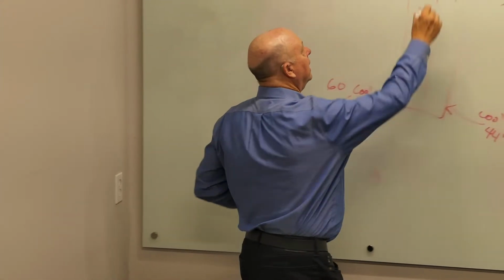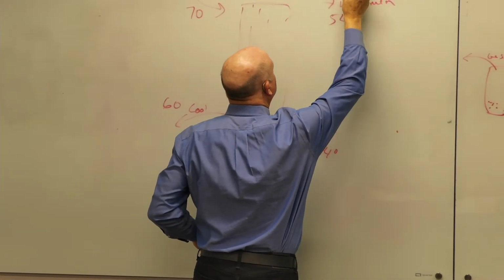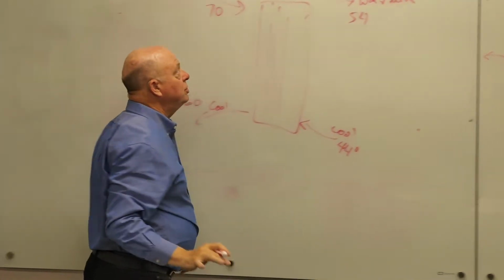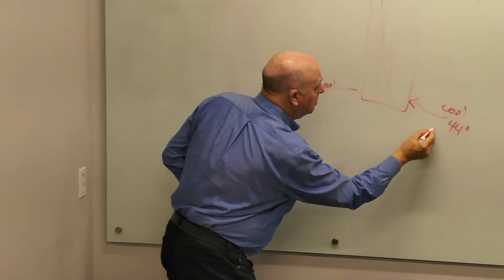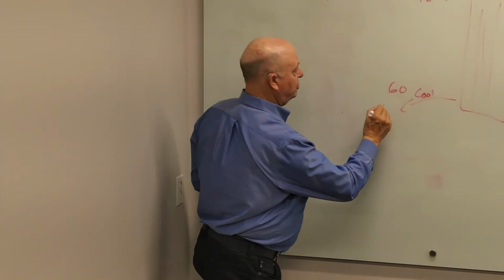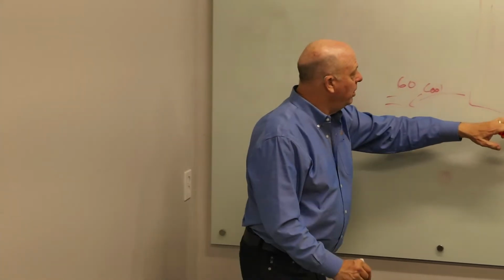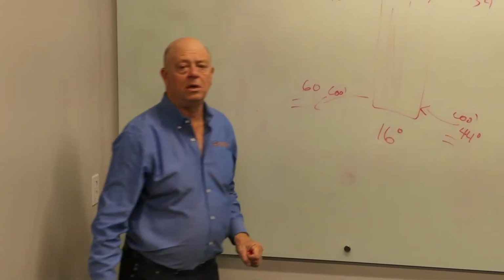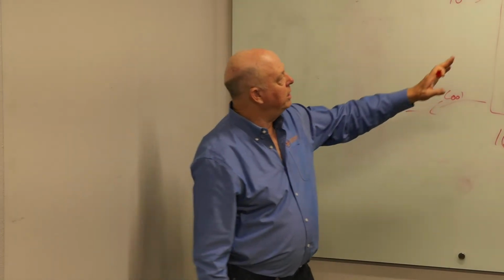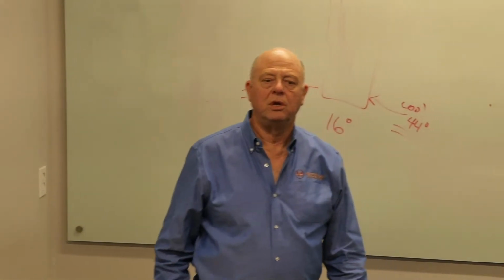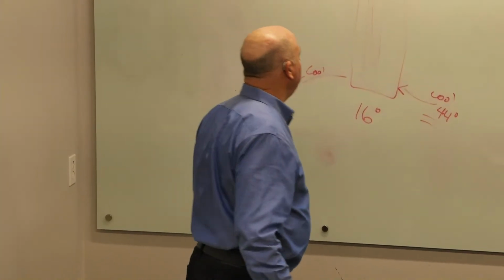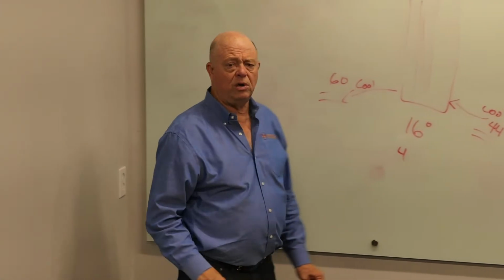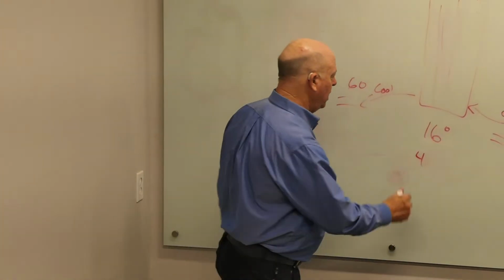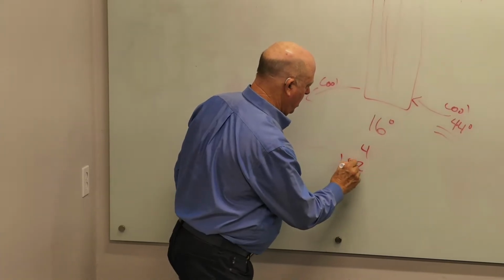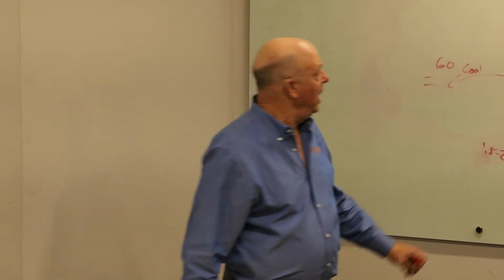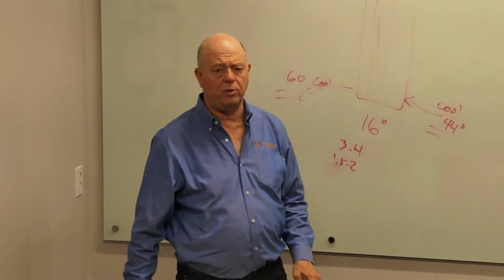Approach. This is a term that all heat exchangers can be rated with. Approach refers to the difference between the driving temperature and the resulting temperature. So in this case, we would have a 16-degree approach. Now in plate heat exchangers that we would ever use, a 4-degree approach would be typical. And if we wanted to spend ridiculous amounts more money, we could get it down to like 1.5 to 2. But that's not linear either. So the typical heat exchanger we would use would have somewhere between a 3 and a 4-degree approach.